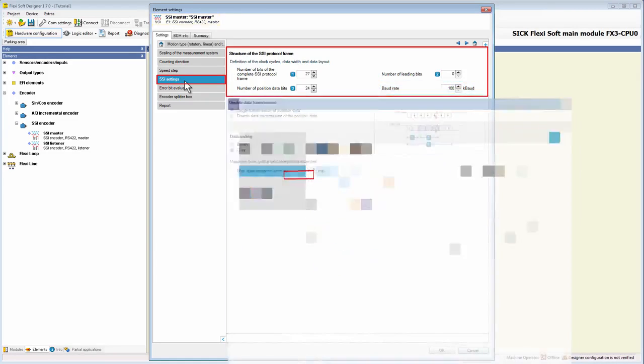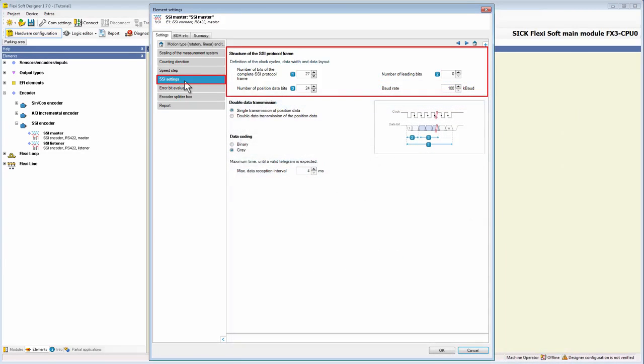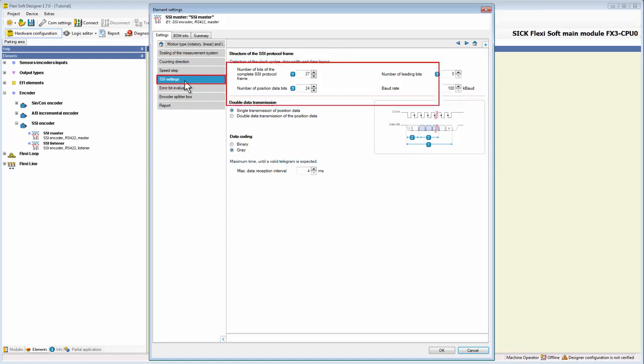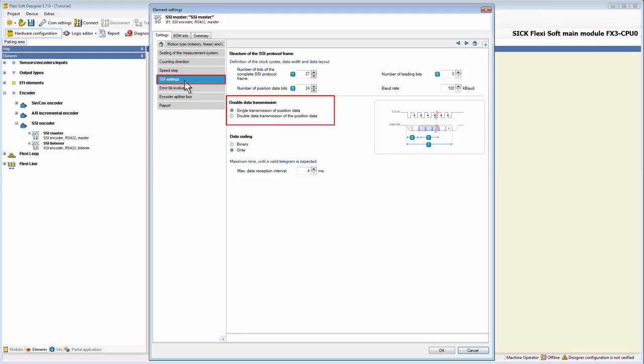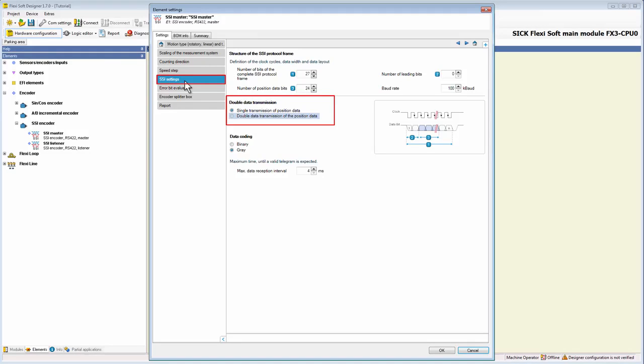Let's go back to the tab SSI settings of the SSI master and take a look at the settings about the data transmission. Here we can select if the position value is transmitted once or twice in the SSI protocol frame. If double data transmission is activated, the MOX module checks if the two values for the position data in the SSI protocol frame are identical. If they are not identical, the position data from this SSI protocol frame will be ignored.